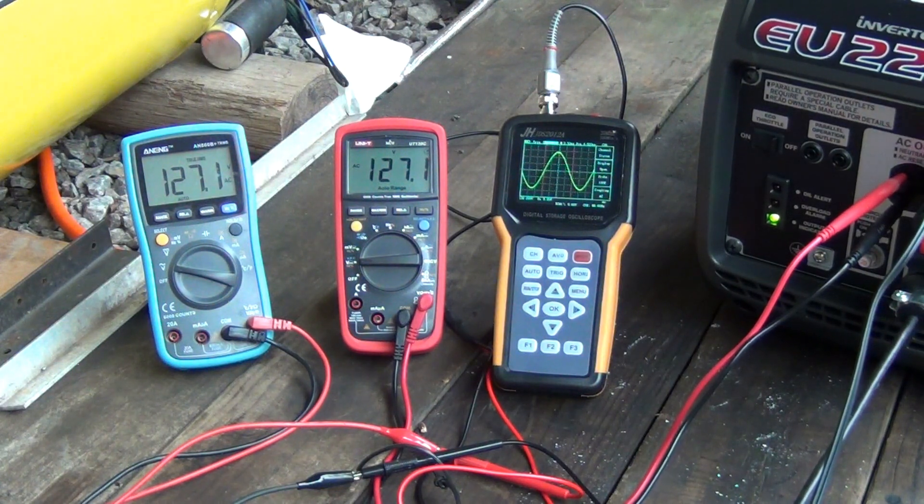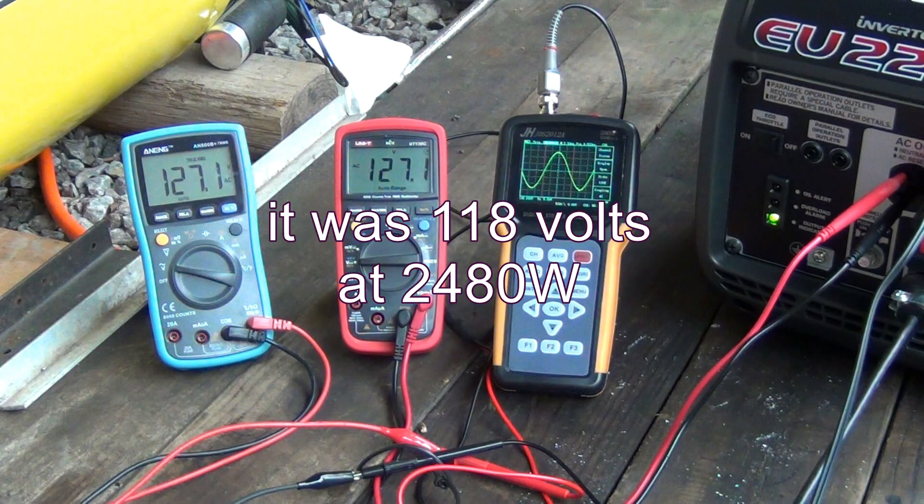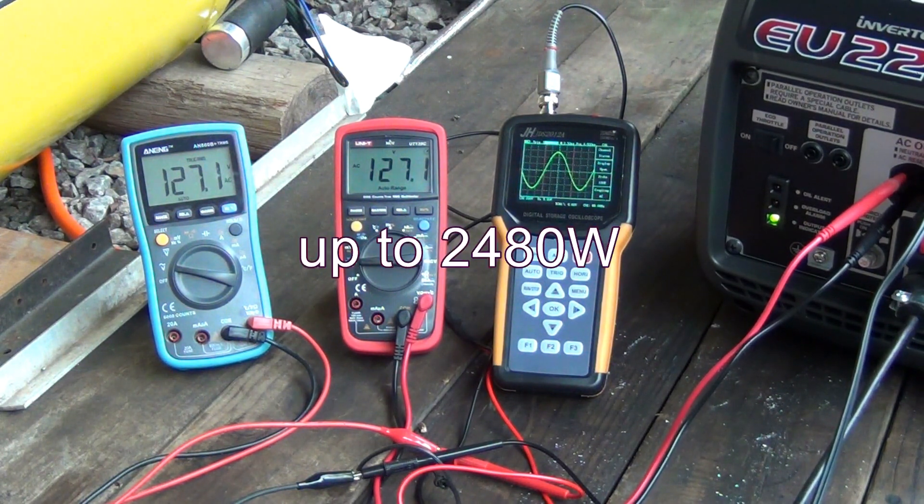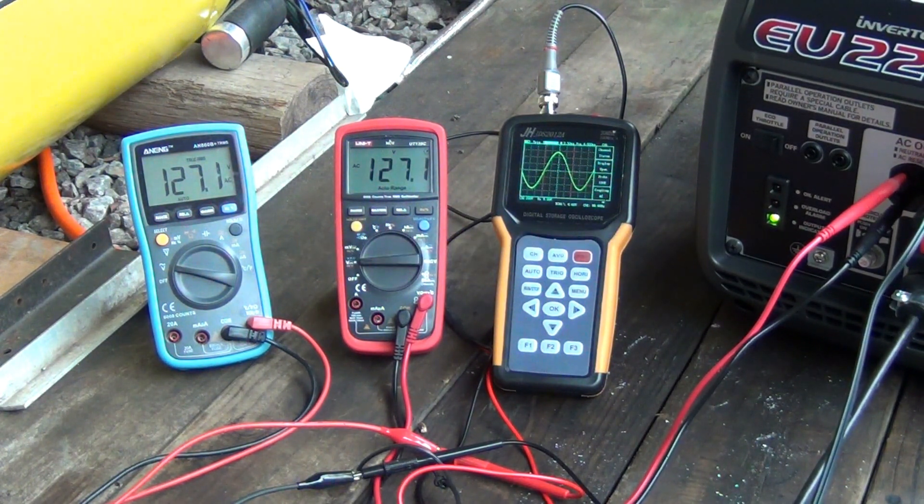As you can see, there was a significant voltage drop to about 118 volts — that's still pretty good. The generator was actually holding really well up to 2480 watts, and then when I jumped to 3000 it went into overload. I hope you enjoyed it — till next time.